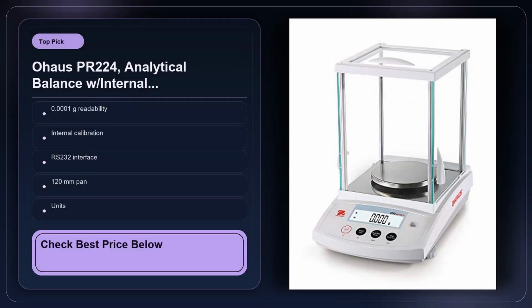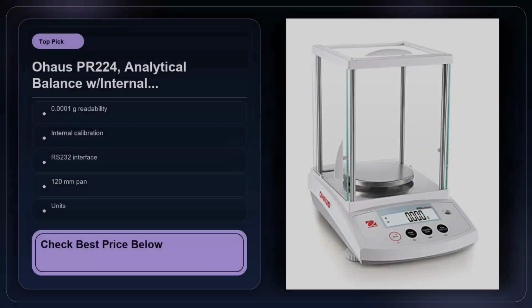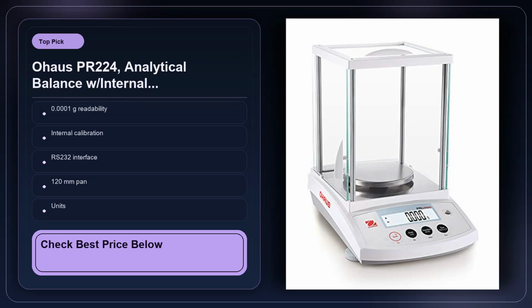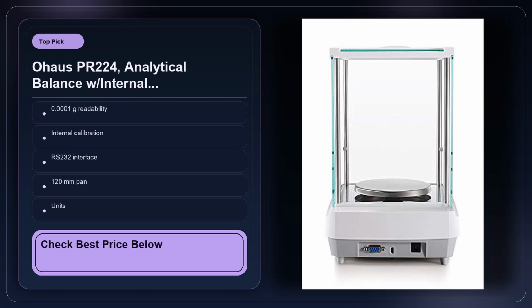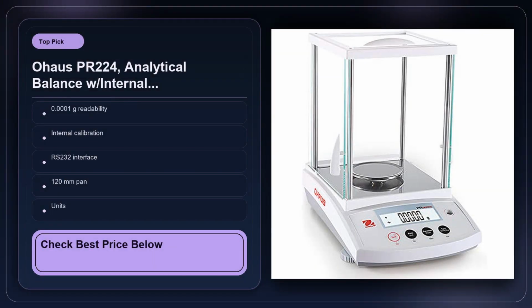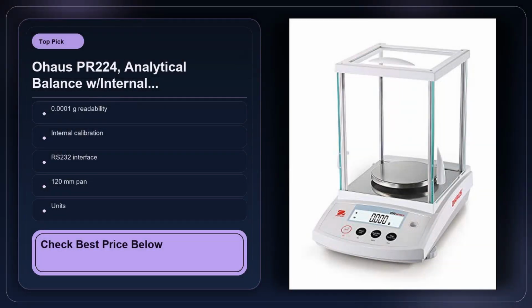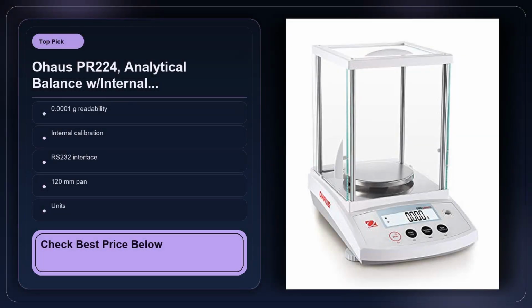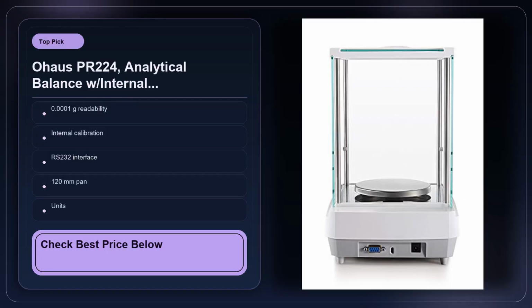One of the strengths that becomes evident right away is the balance's interface. The digital display is clear, with a backlight that stays bright enough even when you're working under a fume hood with the lights dimmed. The unit selector lets you toggle between grams, milligrams, and micrograms without digging through menus, which is a practical win when you switch from weighing a bulk reagent to a trace impurity. The pan size, while modest at around 55 mm in diameter, is just right for standard weighing boats and small weighing papers. It won't accommodate a large beaker, but you're not buying an analytical balance to weigh a beaker anyway, that's where a top-loading balance belongs.